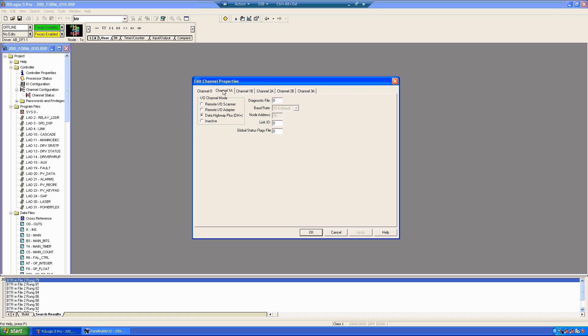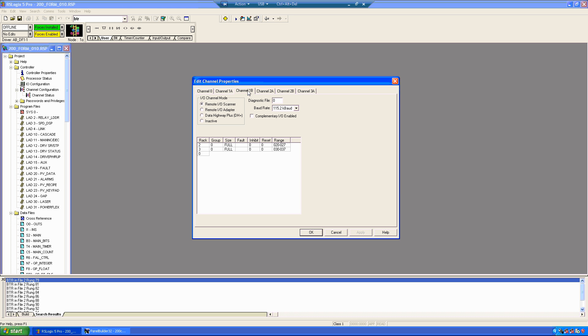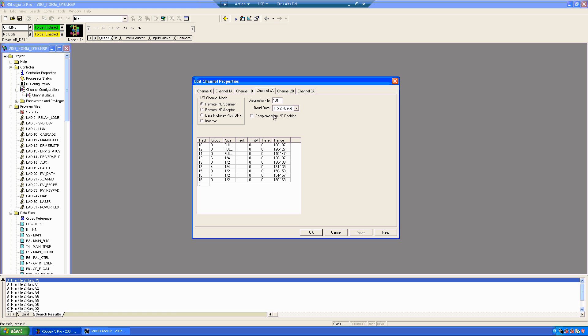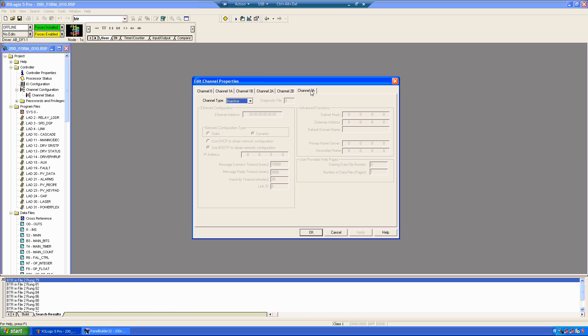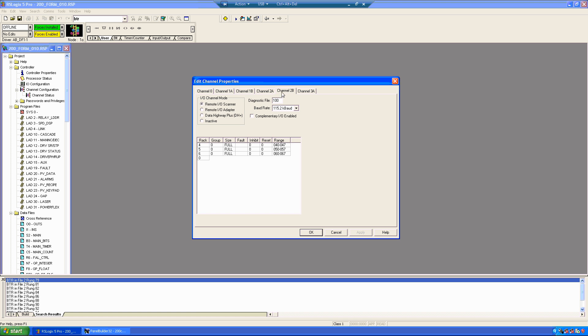So, then if we go to each channel, 1A is assigned to DH Plus in this application. 1B is a remote I.O. channel as the scanner, 2A is remote I.O. as the scanner, and 2B is remote I.O. as the scanner. And we don't have Ethernet on this. There's no Ethernet card installed on it.